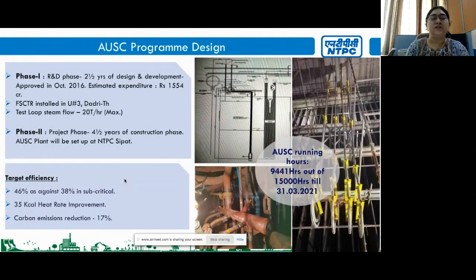We have installed a test loop of this in its phase 1. NTPC has installed its test loop in unit 3 of NTPC Dadri, and it has to be tested for 2 years, and we have achieved the running hours of AUSC of 9,441 hours. After its test results are proven, NTPC will go in its phase 2 and we will set up an AUSC plant in NTPC Sipat. This plant will have the highest efficiency among all coal stations. It will have 46% of efficiency as compared to 38% in subcritical and supercritical plants. Also, it will give us a 35 kilocalorie heat rate improvement, and it will reduce our carbon emissions by 17%.